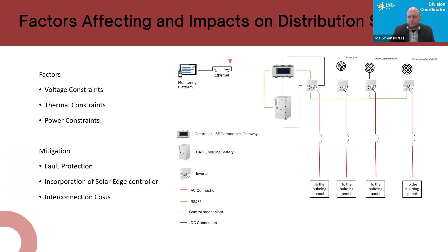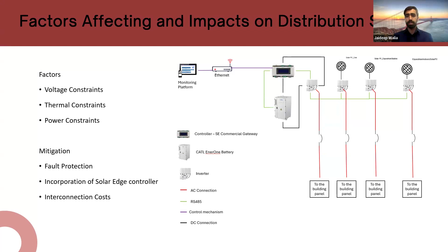We considered several factors as part of the distribution system impacts, including voltage constraints, thermal constraints, and power constraints, along with mitigation factors like fault protection. We've incorporated a solar edge controller to avoid power backflow, and reduced interconnection costs by using existing nodes, placing the battery system next to the geothermal plant where it's needed. We've also included the signal diagram for reference.